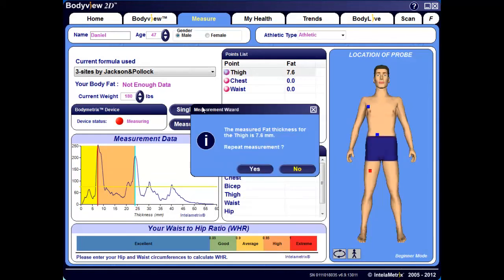This technique is called averaging, which gives you a signal in the measurement data graph displaying clearly defined characteristic peaks. The first strong peak is generally the fat-muscle interface, which lines up nicely with the red vertical line, displaying the fat thickness at 7.6 millimeters here in yellow. The second peak is a boundary between two big muscle groups, the vastus lateralis and vastus intermedius.